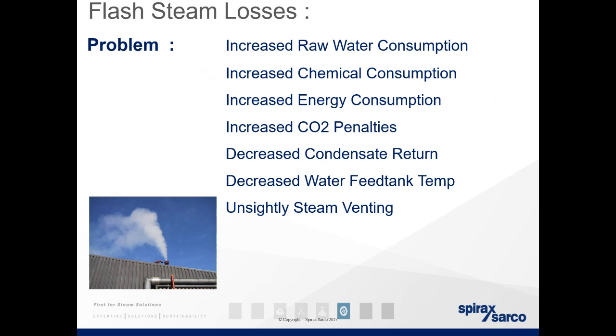So flash steam losses, the problems. So increased raw water consumption. If you take the picture in the bottom left-hand corner here, this is an example that will give you an indication you're losing a lot of steam. We will see some of this normally anyway. If you have an open to atmosphere tank, you will always see flash off, but it's trying to minimize that loss. Increased chemical consumption, as Anthony spoke about earlier as well. So the more raw water you're having to add to your system, the more chemicals you're having to use. Increased energy consumption, we covered earlier, and increased CO2 penalties. That's probably not so relevant for this part of the world where we don't have the CO2 penalties, but I imagine over the next 10 years we will start seeing charges for the amount of CO2 you're releasing.